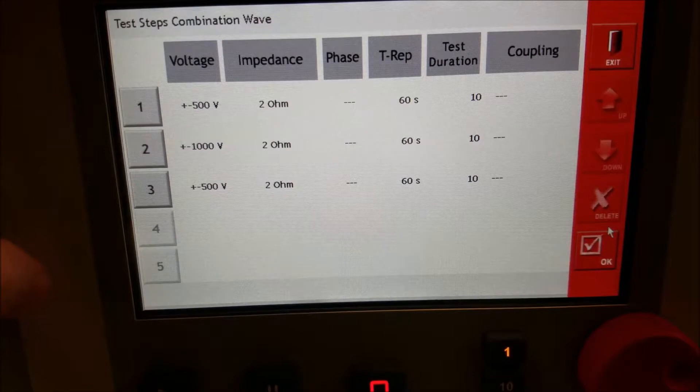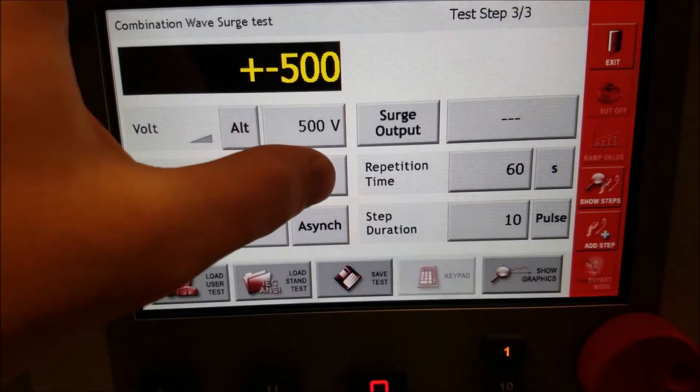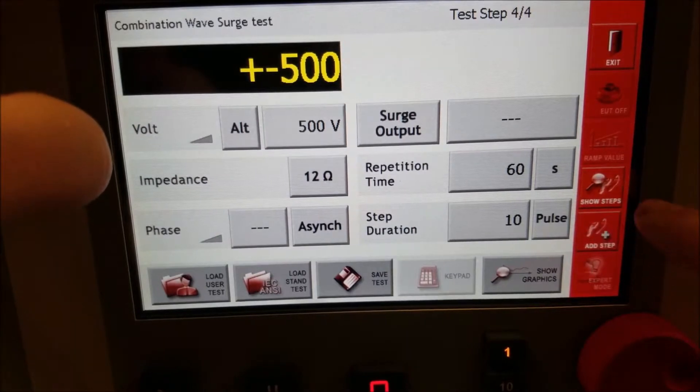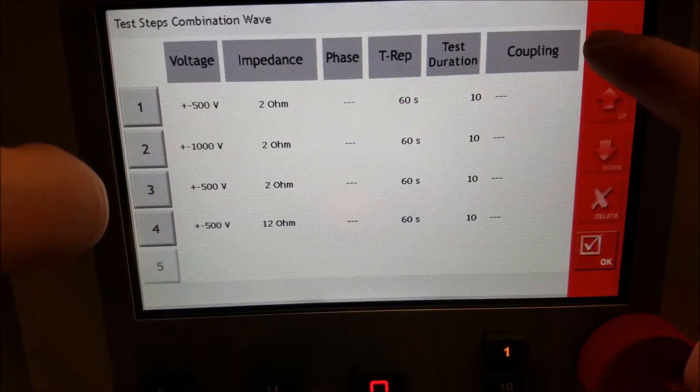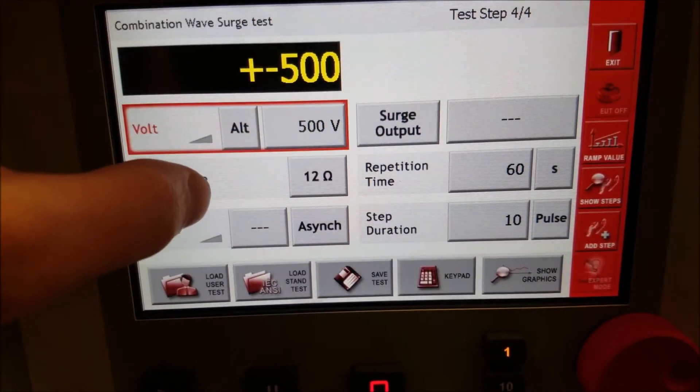Here you can see I just clicked add step, which added the same as step 1, which is 2 ohm 500 volt. Say I want to jump to a 500 volt 12 ohm surge — we can make that our next step. We can save these and load them later on.